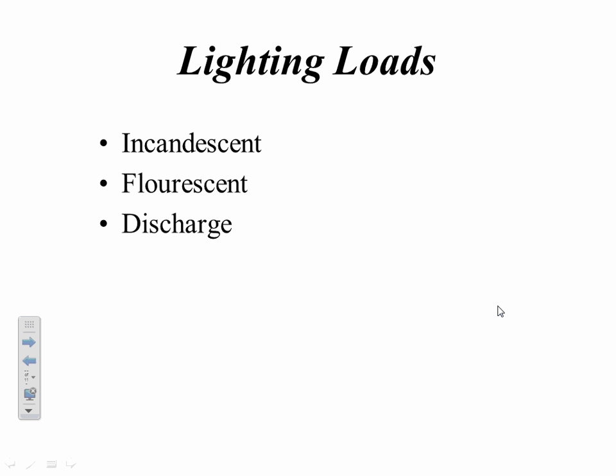Lighting loads. We talked a little bit about discharge lighting when we were talking about closed transition transfer switches. That's a good application, discharge lighting. Anything that needs a restrike time, if we can hit it with something that doesn't interrupt the power, all the better.